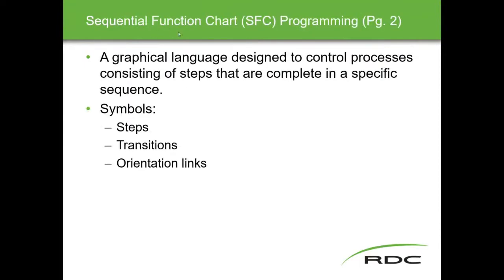Okay, so what is a sequential function chart, or SFC? It is a graphical language designed to control processes that consist of steps that are completed in a specific sequence. I have a slide at the end that tells you where sequential function charts shine, but this is a clue here: processes that consist of steps to be completed in a specific sequence. So batch processes are good examples, startups, shutdowns, manufacturing lines, things like that, where things have to be done in a certain number of steps.